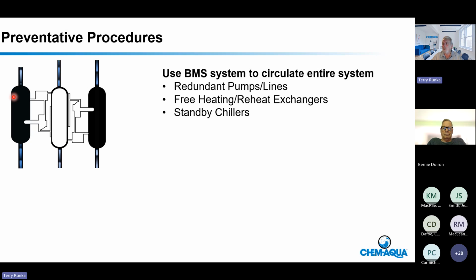So what we're trying to work out with each place, and it's in your management plan because it's all different, is to work with your building management system to see if there's some way you can get all the pumps running. You don't need the fans running, but if you've got free heat or free cooling exchangers, heat reclaims, there are all kinds of places that water goes that doesn't necessarily circulate all the time. What we want you to do is figure out a way to turn on all the pumps so that all the water in the system circulates at one time. Let us know when that is.